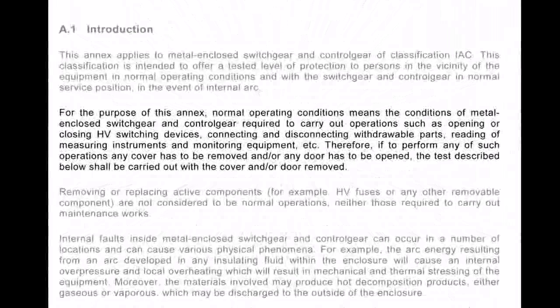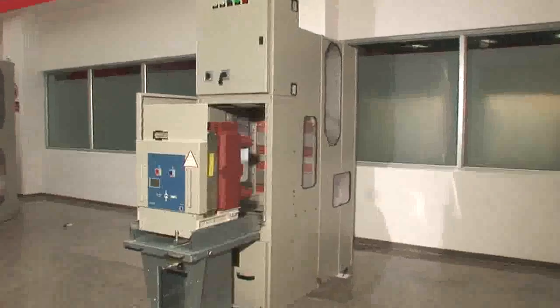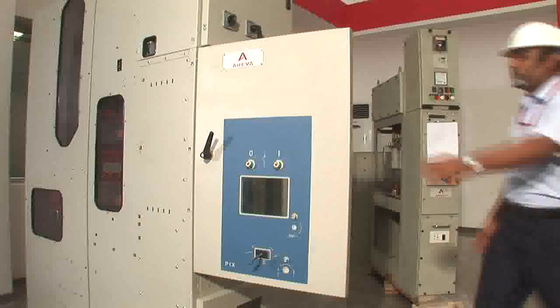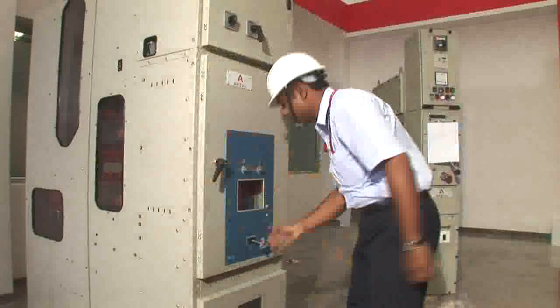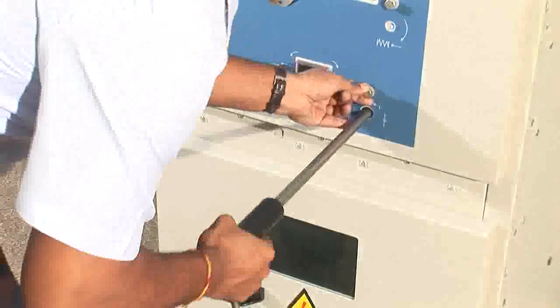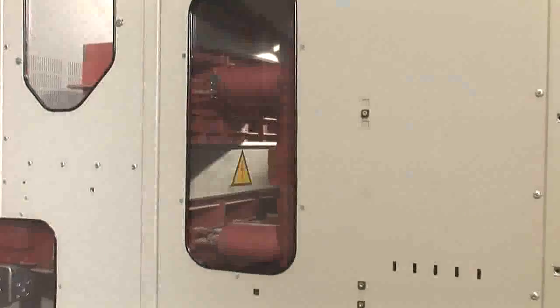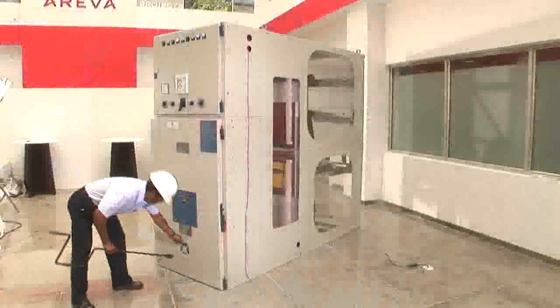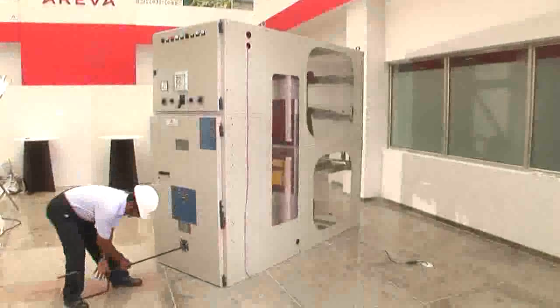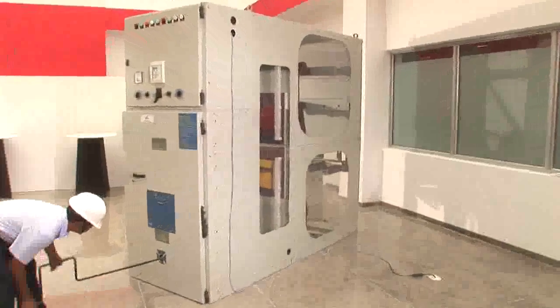This means that if the door of the switchgear had to be opened for operation, then safety-related tests like internal arc had to be performed with the door open. This indirectly implies that all operations behind a closed door become a mandatory feature for all switchgears. This translates into the fact that the operator is safe thanks to the tested enclosure and the door interlocks, which prohibit any operation which is risky to be performed while the door is open.